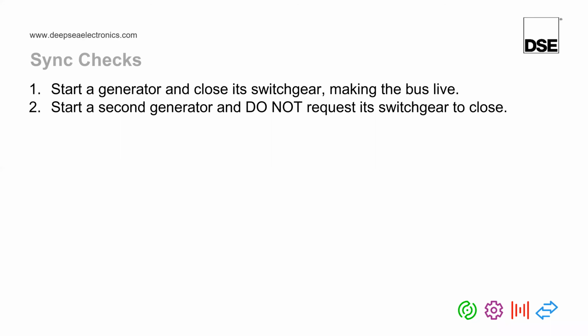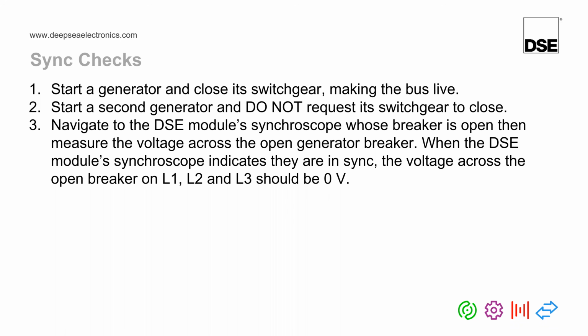We then start a second generator and we do not close the generator breaker. That's very important because all the way through this procedure so far, our generators have not been placed in parallel. Every step we've done so far has been done on each generator in turn in isolation. We then navigate to the synchroscope on the DeepSea module's display, which you can see even if the DeepSea module has not been requested to synchronize. And then we measure across the open generator breaker for L1, L2, and L3. When the synchroscope shows the phase dot in the middle, you should be seeing roughly 0 volts across the open breaker.